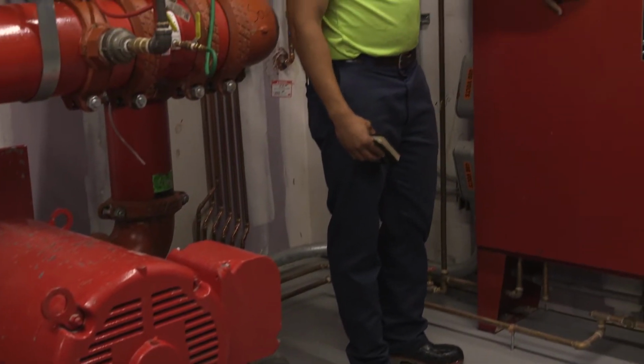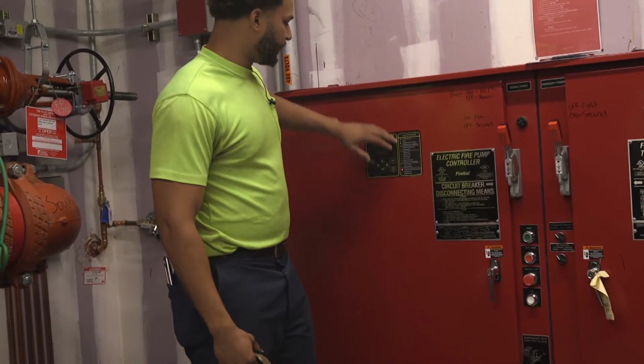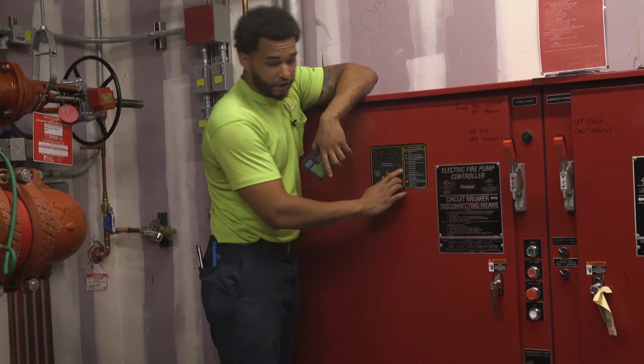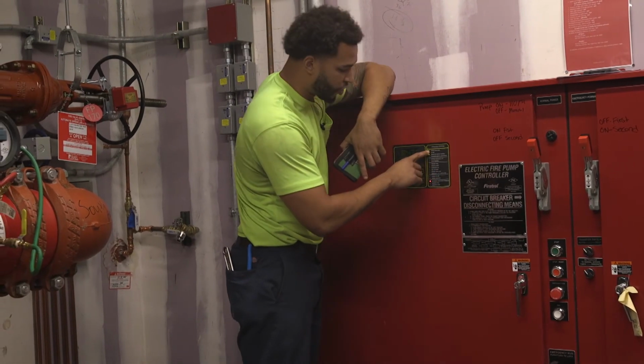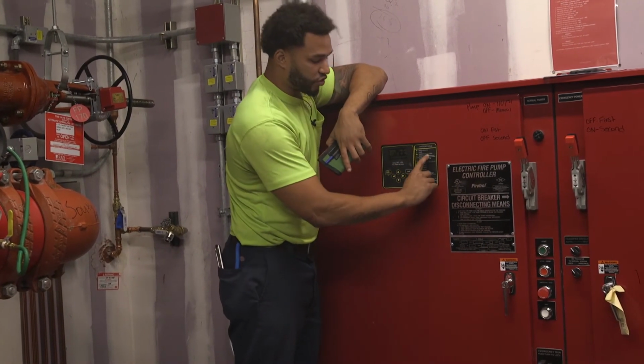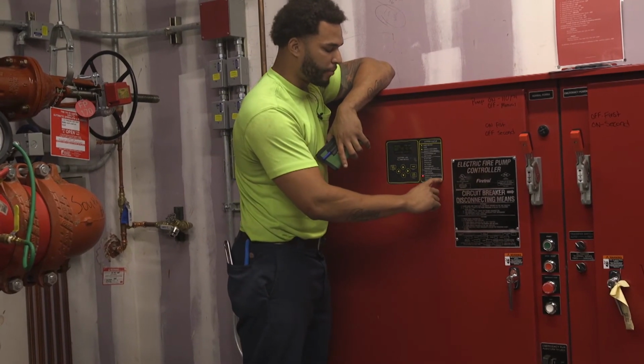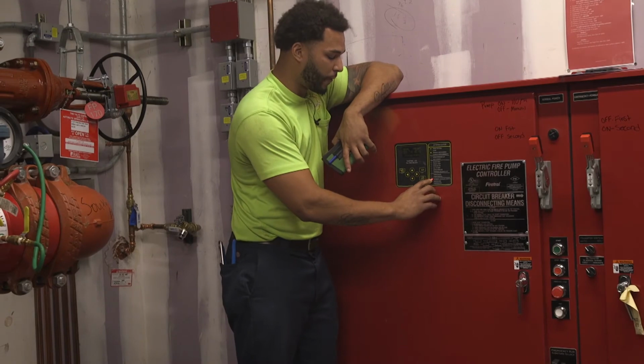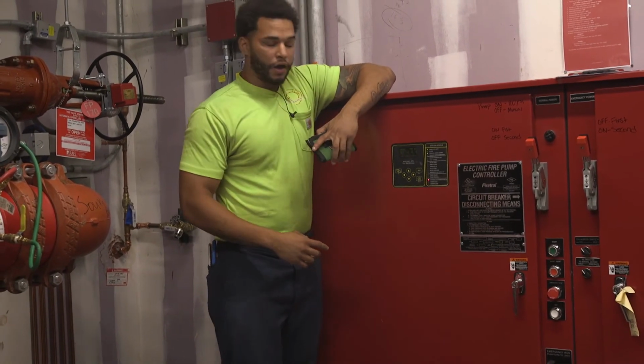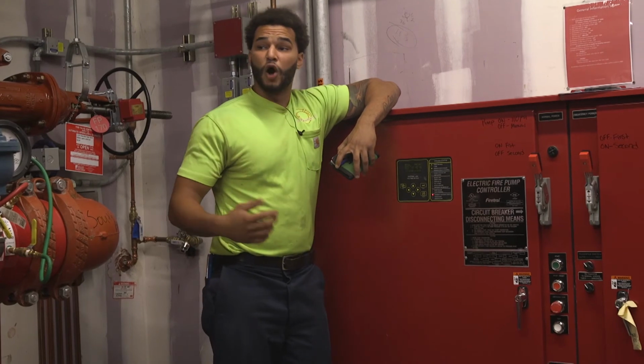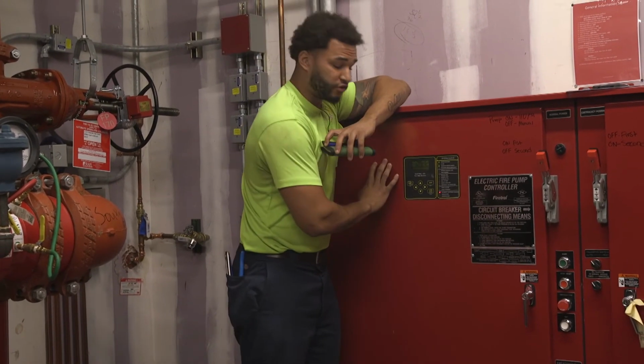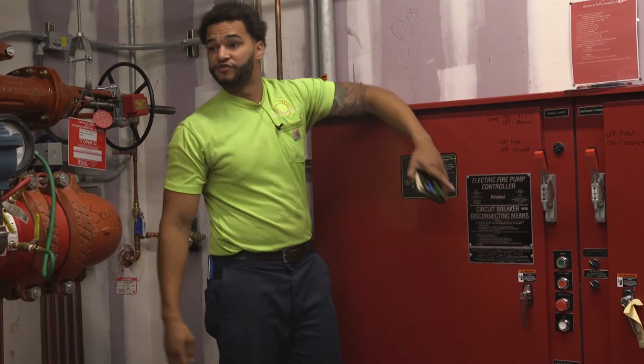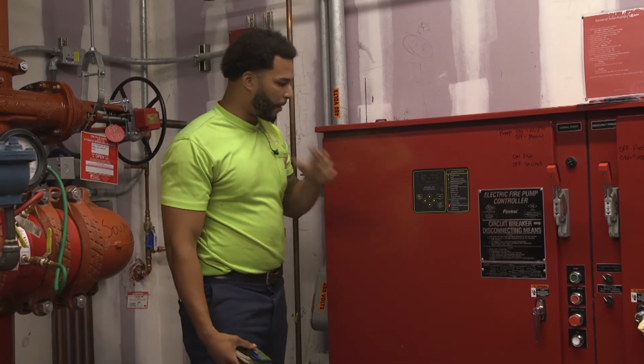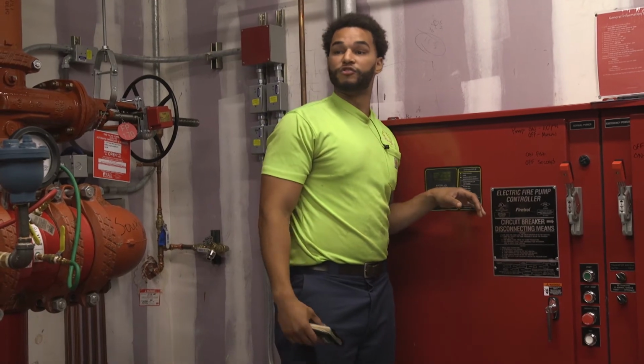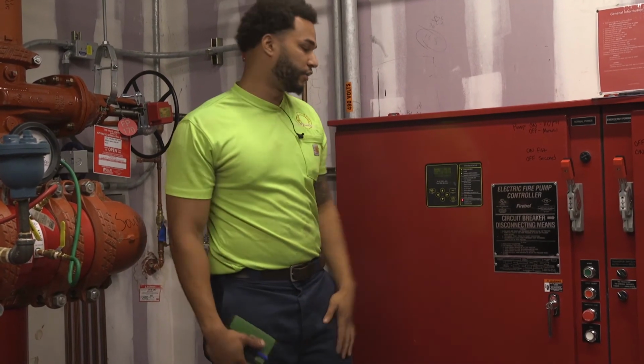So I want to turn the fire pump on again. So if you guys look here, this is where we should look in normal operation, normal conditions. We have our power available LED on. We have our transfer switch normal LED on, and we have our automatic shutdown disabled LED light on as well. This automatic shutdown, meaning in New York City code, all fire pumps have to be automatic on, manual off. So if this fire pump was to operate, we're gonna have to manually come down here and push that stop button to stop the fire pump. And that is being, we realized there's no fire, and it was just the fire pump is running for whatever the situation was at that point.